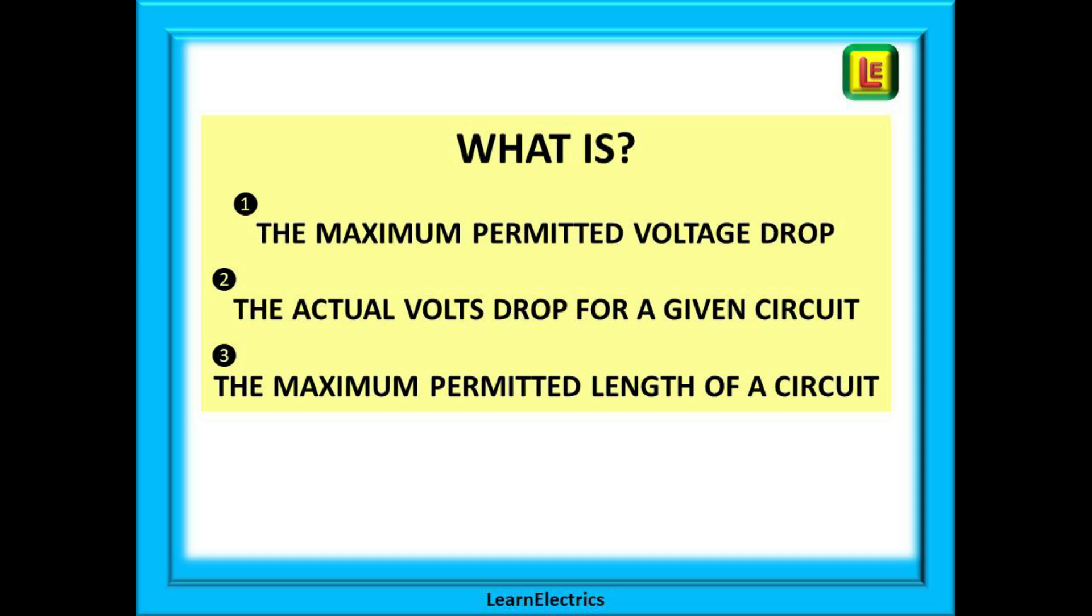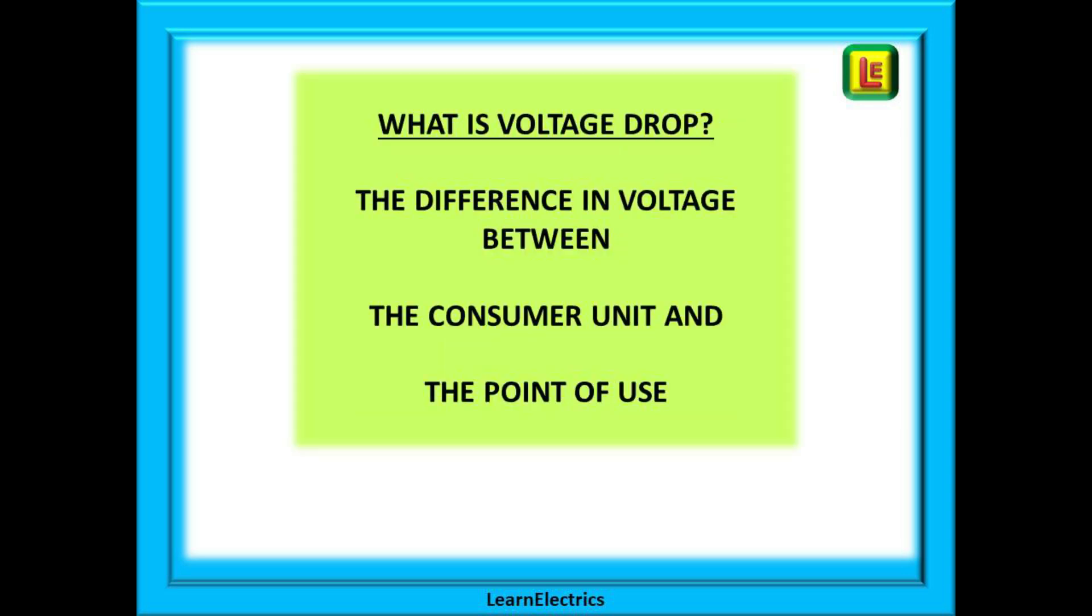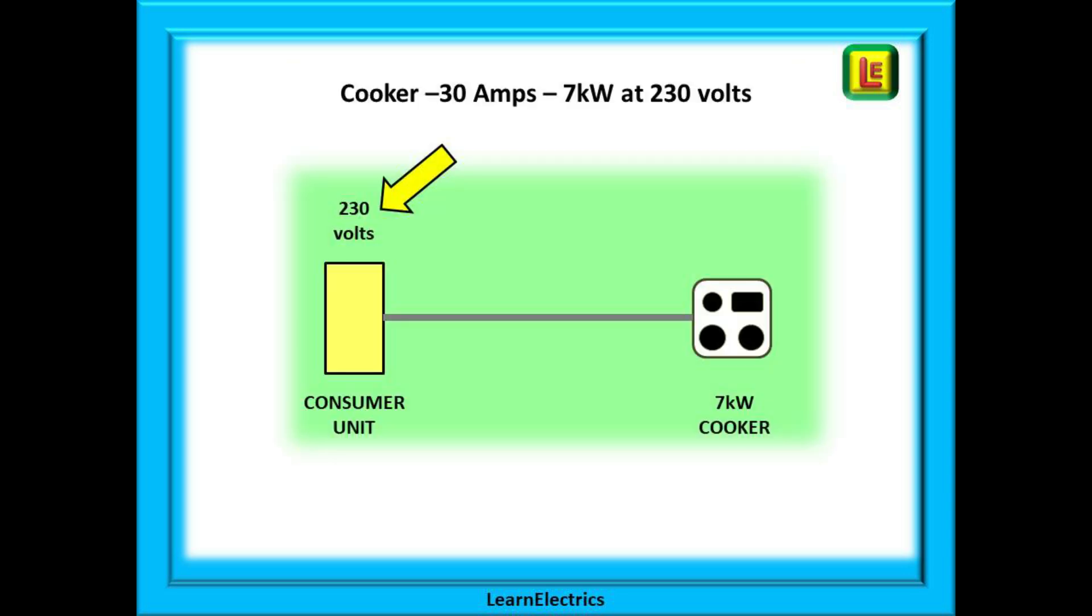If you know how to find these three answers you really have cracked it. Let's begin with a quick understanding of just what voltage drop is and how it affects cables and circuits. What is voltage drop? It is simply the difference in the voltage between the consumer unit or distribution board and the furthest point of use on each circuit, for example the cooker, the shower, the furthest light, the electric gates, and so on.